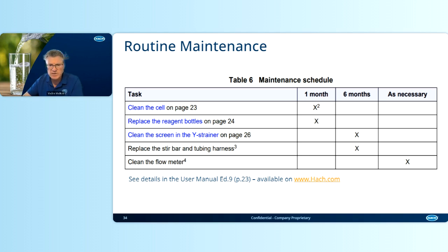It may vary, it may be 3 months when the conditions are not ideal, and cleaning the flow meter as necessary. And as I mentioned, for cleaning the flow meter, we have documents outlining the guides, the functions, the steps, everything, and it can be bypassed if it creates that type of nuisance. However, with bypassing the flow meter, as I mentioned, you may lose valuable functions of this device.